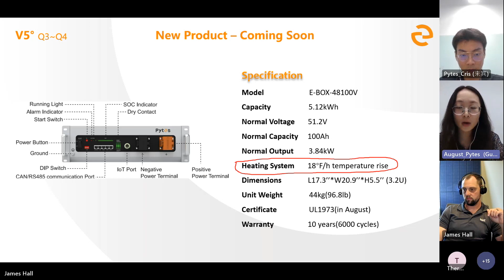A very big feature I want to highlight is that this is designed for a wider range of temperatures. When the cell temperature is colder than 41 Fahrenheit (5 Celsius), the heat will turn on. When the cell temperature is higher than 50 Fahrenheit (10 Celsius), the heat will turn off. But when the cell temperature is colder than -4 Fahrenheit (-20 Celsius), the heat will never turn on. This is how it works in different environments.